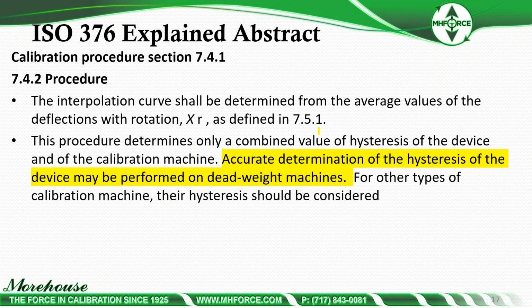For 7.4.2, the interpolation curve shall be determined from the average of deflections with rotation XR as defined in 7.5.1. So if we go and look at 7.5.1, that's basically going to tell us that we can use a first, second, or third order equation. And that's important to note because other standards allow higher order equations where ISO limits it per that section to just a 3rd degree only.